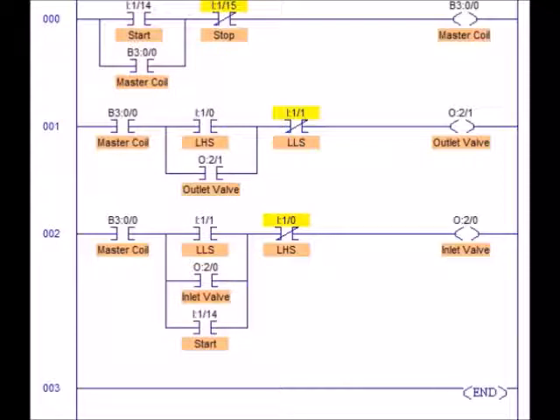Similarly, on rung 2, the inlet valve is energized when the low level switch is triggered and energized, allowing water to fill the tank. The inlet valve will only de-energize to close when the normally closed level high switch is de-energized when triggered. In addition, in this rung, there is another parallel branch which allows the inlet valve to open and fill the tank on start.